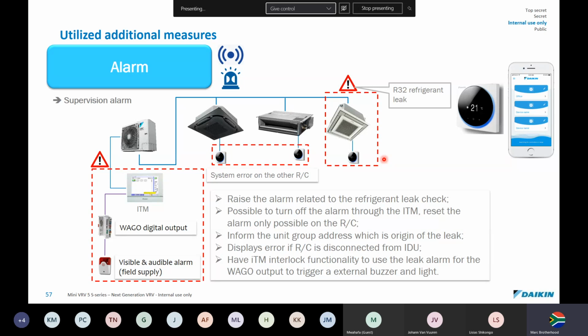Further to this, you can add the iTouch Manager onto the VRV5, and there will be an output. Once this receives a leak alarm, you put that into a WAGO module, and that WAGO module then makes or breaks. It's digital, so it's going to fire a switch, and it's going to trigger a third-party alarm if you want.